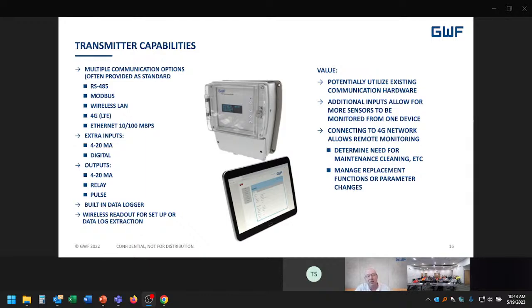These systems also have built-in data loggers, so guess what? If there's a problem, download the data. It helps us see what is happening within the device. From a service point of view, being able to capture that data is very important for us to be able to see if there is an issue or what may be going on where there's a concern. And also some of these systems have wireless readouts. So I know that ours have built-in Wi-Fi routers, which means you can use a tablet, go up to the system and log in as a tech and pull data without having to unplug things, without having to try and change the settings of the system. You can do it straight there and then right on top of it.